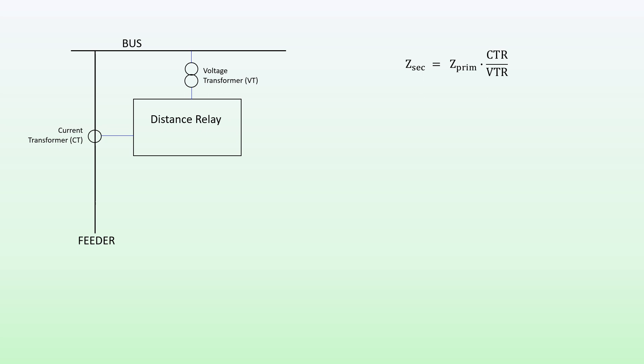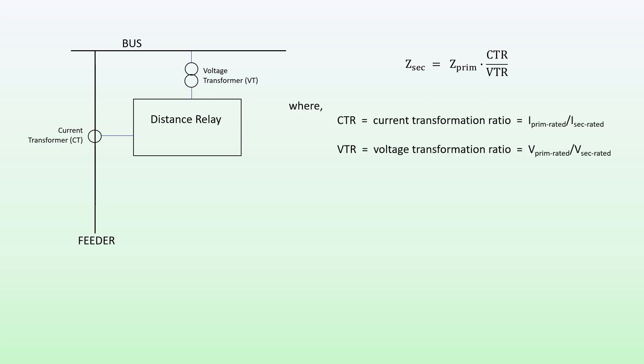What I'm going to demonstrate is that the secondary impedance — that is, the impedance as seen by the relay, or the measured impedance — is equal to the primary impedance times the CT ratio divided by the VT ratio constant. The CT ratio is the rated primary current of the CT divided by the rated secondary current, and similarly the voltage transformation ratio is the rated primary voltage divided by the rated secondary voltage of our VT.